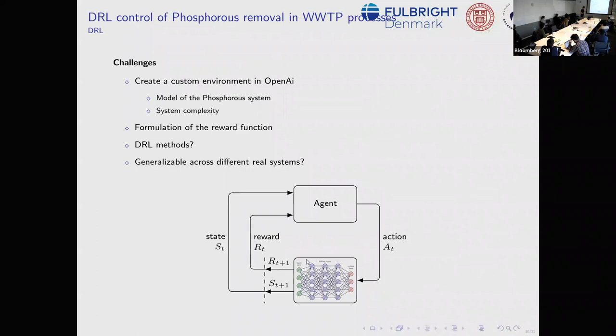We're actually training a reinforcement learning policy to control phosphorus removal as part of an EU Marie Curie project called RECAP — recapturing phosphorus. Our job is to improve the injection of chemical — iron phosphate — to settle and separate phosphorus for recapture. We control the chemical injection based on the phosphorus measurement. Essentially the RL agent overrides the PID controller — right now it's simulation, on a computer far from anything real.